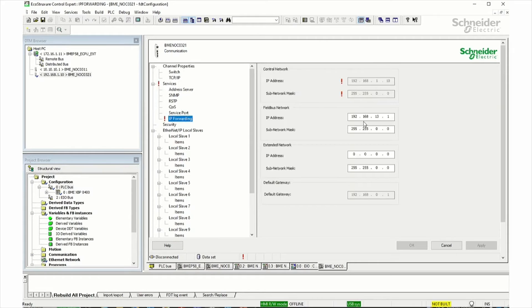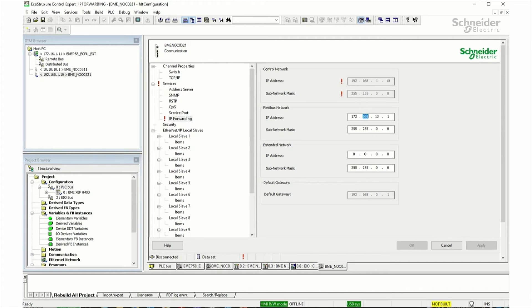And in here, we need to set up the correct gateway IP addresses for the device network and for the extended network. So in this case, it will be here the M580 gateway IP address, which is 172.16.3.1. And for the extended network, it will be the NOC311 gateway address, which is 10.10.0.1. Click Apply.